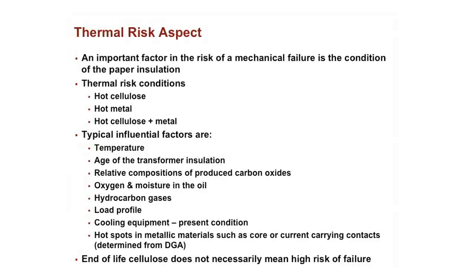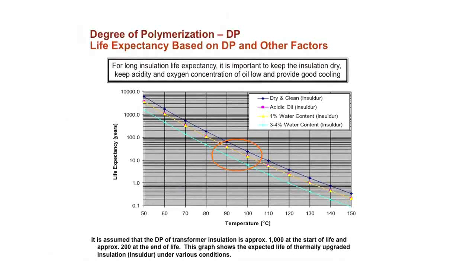One thing we talk about a lot is this degree of polymerization. This basically talks about the age of cellulose. When you start out with new cellulose, you have a DP value of about 1100, and when it gets down to about 200, that's when it's reached the end of its life. And what accelerates that aging is having high moisture or high oxygen.